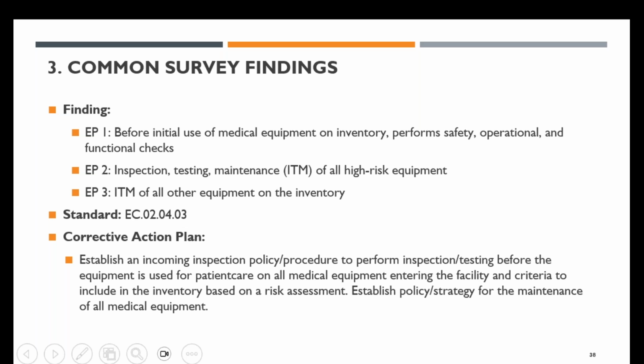You can set up a way in your CMMS system so that as soon as a new device is created in the system, an incoming inspection work order is generated. Someone has to acknowledge the work order and make sure the proper asset tag, control number, or PM, all the things, are categorized. If there is acceptance testing or a vendor report as part of the new equipment, it's all tied into that incoming inspection work order, and you are closing it.